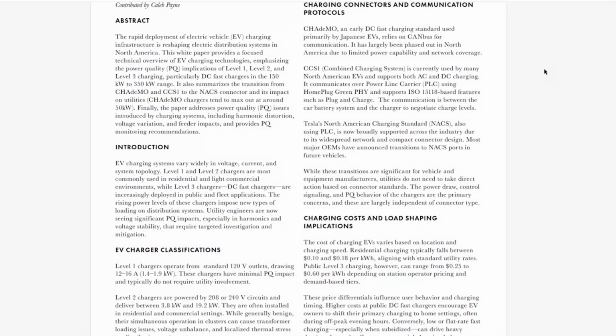One of the fascinating things is that Tesla, being the largest manufacturer and the biggest uptick in EV manufacturing in the U.S., has kind of driven innovation across the field. So their NACS charging systems have become the go-to standard for everybody. So all new vehicles manufactured in the U.S. are going to come with the NACS plugs. And the slowest charge you're going to find for Tesla at this point is 250 kilowatts. So there is going to be probably a fairly dramatic uptick in those. Anecdotally, we're here in rural Virginia in the Shenandoah Valley. Not a lot of public fast charging here. Like I said, the CHAdeMO is being phased out. And so naturally, that's the vehicle that I chose to drive around for the EV testing. So you go to some of the local chargers and those peak out at about 150 kilowatts, whereas the Tesla chargers that are around here are at 250 and 350 kilowatts.